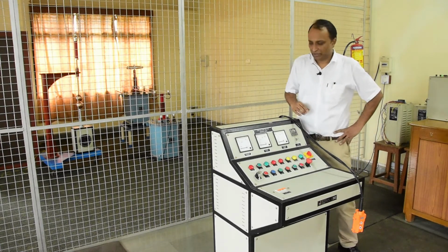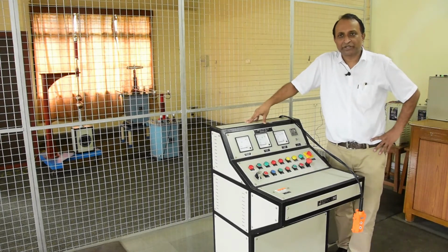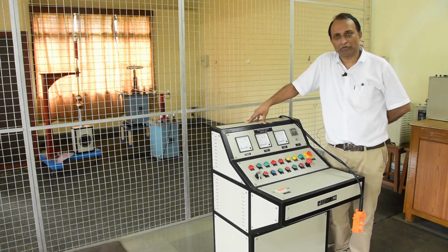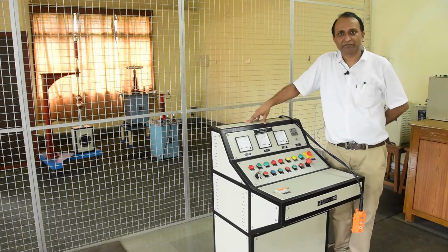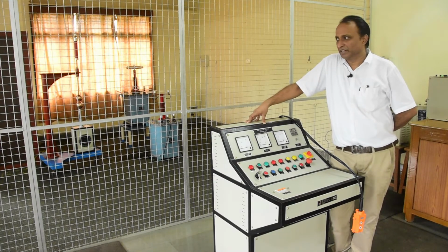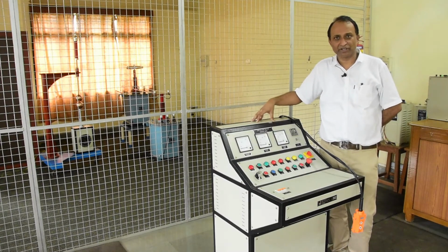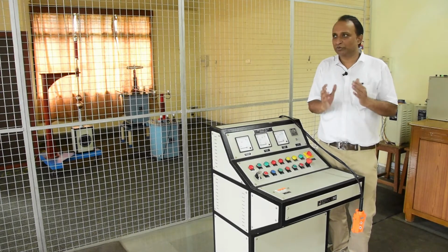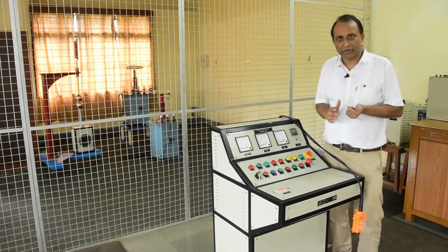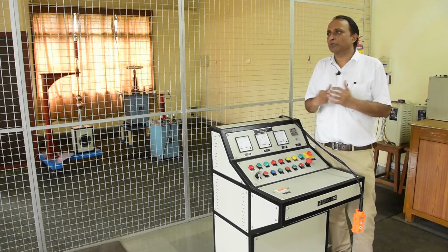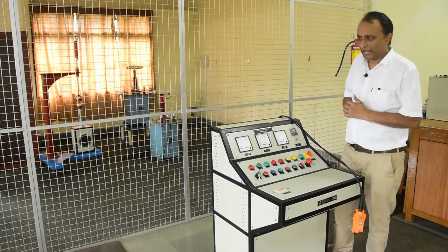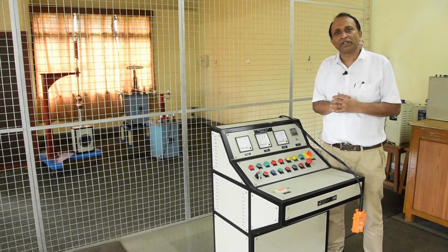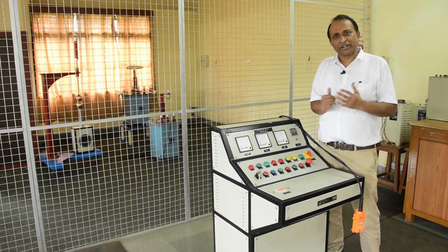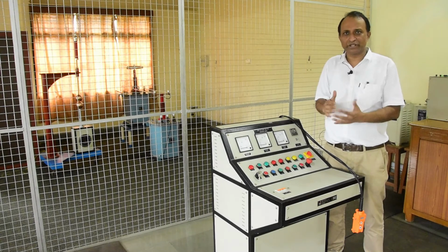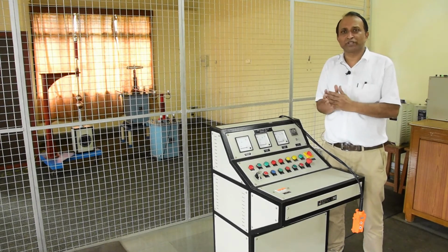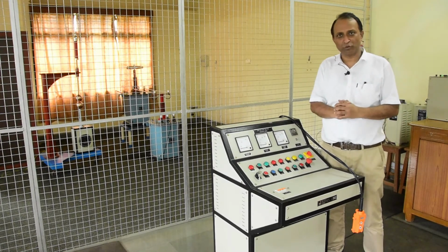Now in this particular experiment, we have to understand that it is about calibration of voltmeters for measuring high voltages. Generally, the common voltmeters used on a day-to-day basis or available in substations are able to measure voltages up to, let us say, 700, 750 volts or 1000 volts. Higher than this, normal power frequency voltages can be measured in labs, substations, power stations and electrical power systems by using potential transformers. In the steady state, the potential transformers step down the voltages, and a voltage of 0 to 1000 volts will be applied. The voltmeter can be calibrated to measure the high voltages.